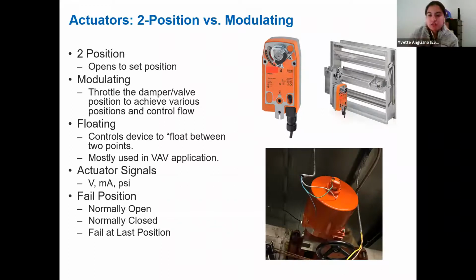So the industry standard for actuators is an electronic actuator utilizing a microprocessor controlled brushless DC motor. And when deciding between two position or modulating, you want the two position for isolation purposes and modulating to throttle air or water flow. And then there's also this third type of modulating, which is called a floating signal. In that case, you'd have two control signals of a 24-volt AC output, and they're sent as pulses to start opening up the damper. And those little pulses are sent slowly to modulate that damper open, or those pulses are then sent again to slowly modulate that damper closed.